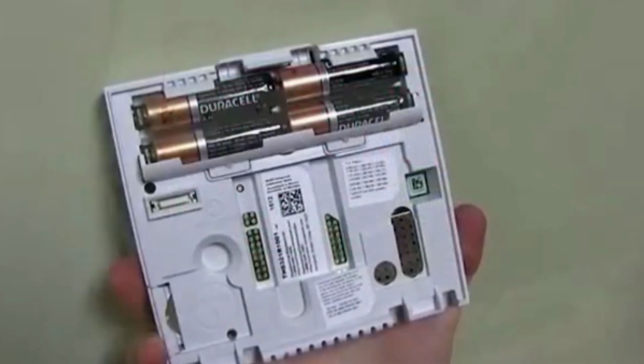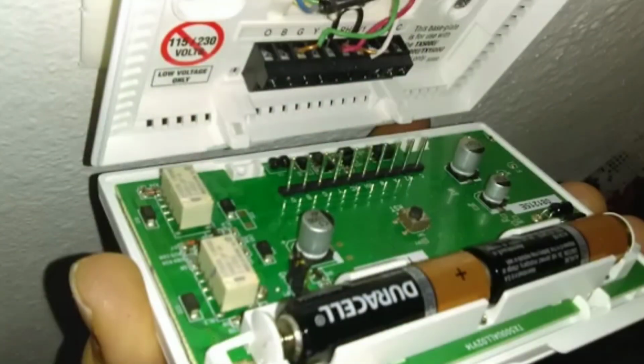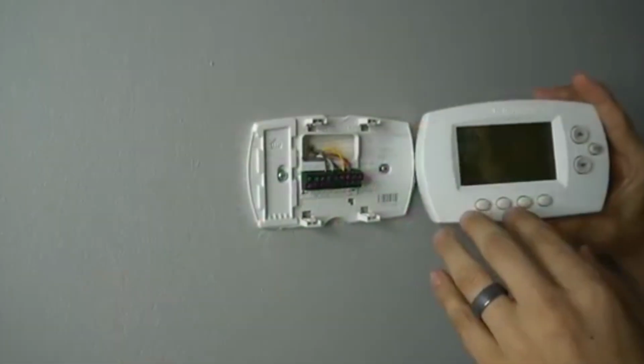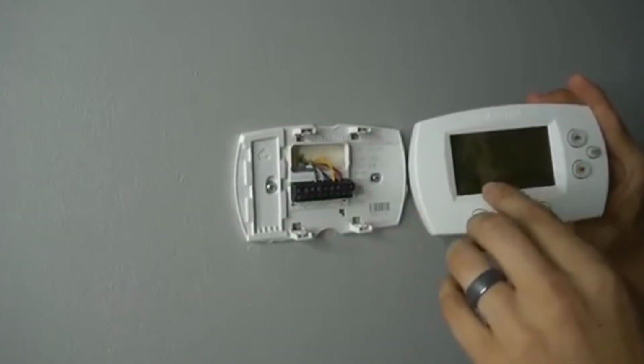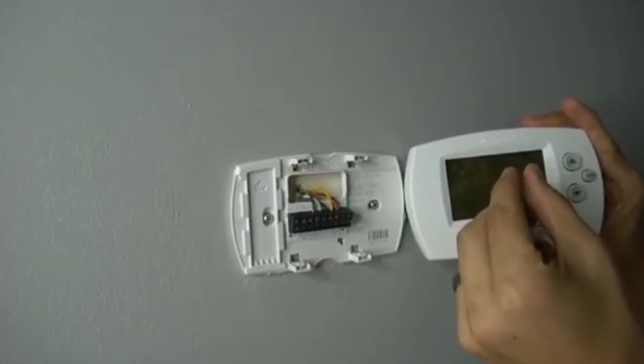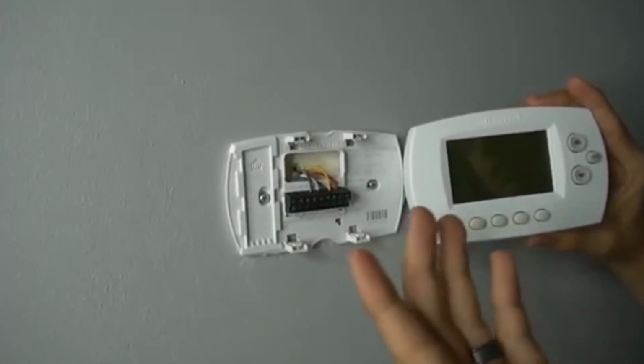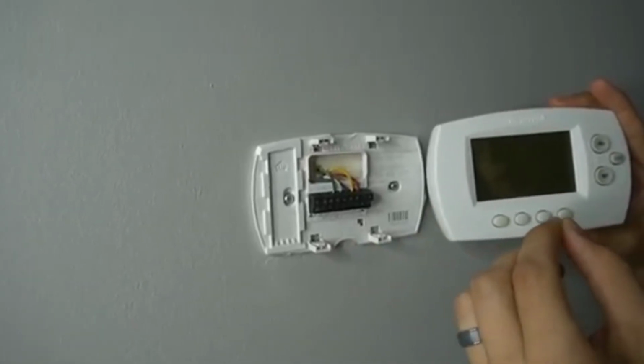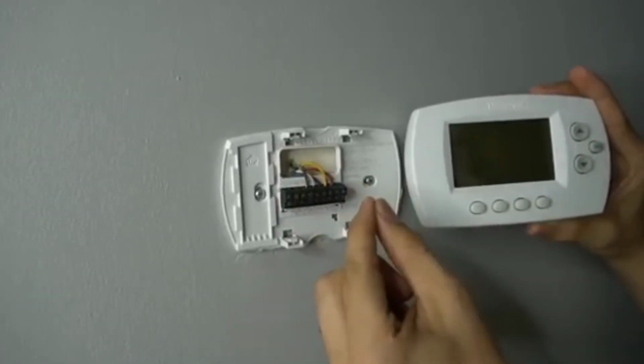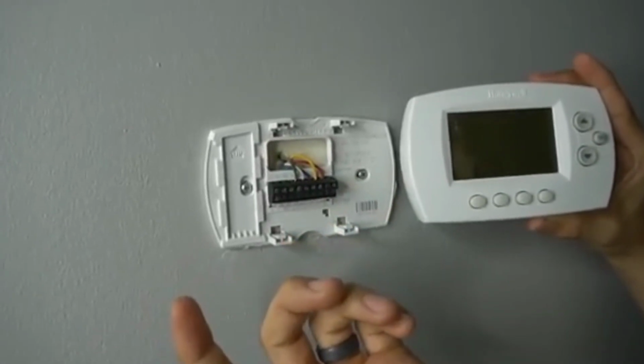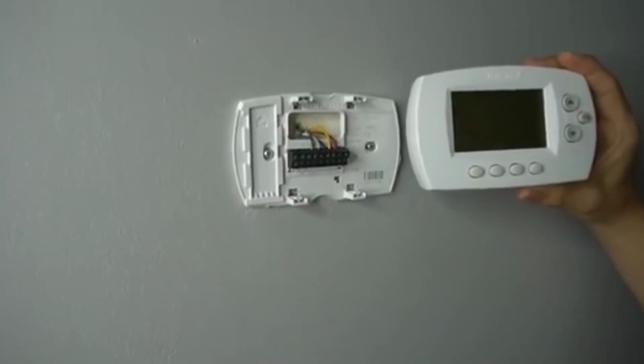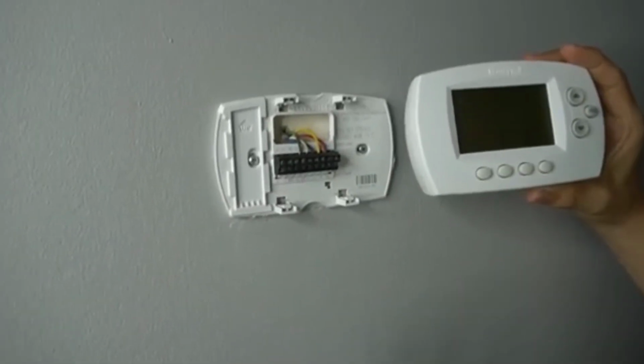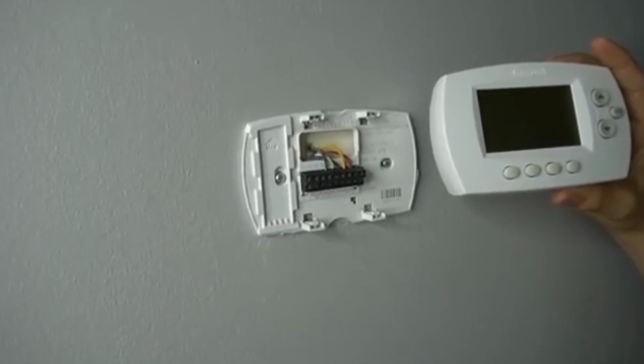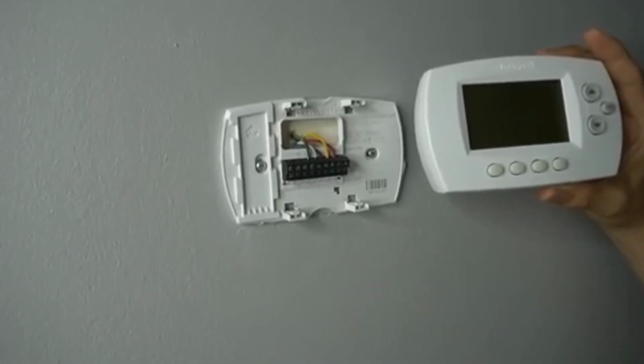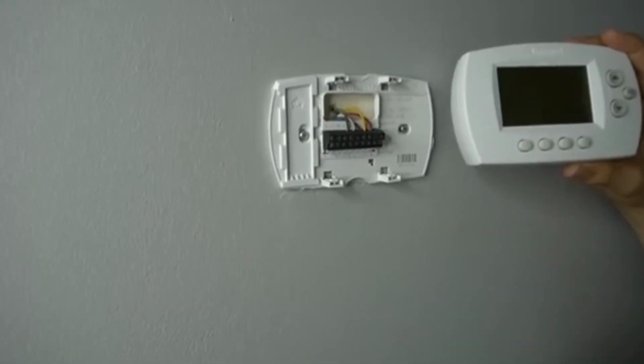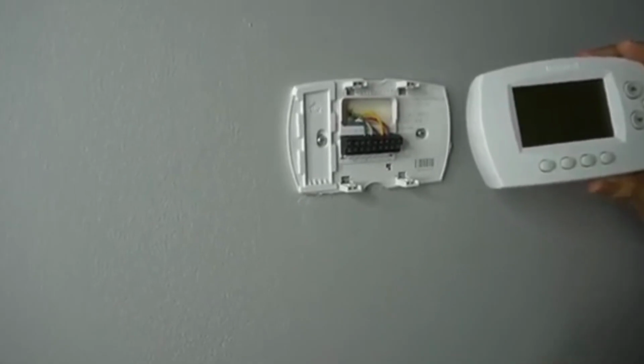But if the batteries in the thermostat become weak or dead, sometimes weak batteries does not mean that your thermostat will die or the little battery icon will show up. If it's weak, it might be just weak enough where it won't close the switch and your air conditioner won't turn on. So if you haven't replaced your thermostat batteries in a while, you should replace them every 3 or 4 years at least, to prevent any kind of problems that might arise down the road.